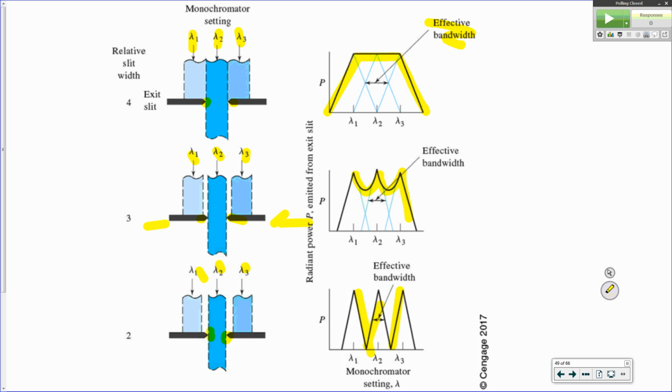So it just depends on the compound that you're looking at and how sharp the peaks are, or the components you're looking at. If they're very, very narrow peaks, you're trying to do an analysis like atomic spectroscopy, then it's to your advantage to use a very, very narrow slit width. If it's molecular species that have big, broad, 100 nanometer wide peaks, you want more power, so you just open it up.